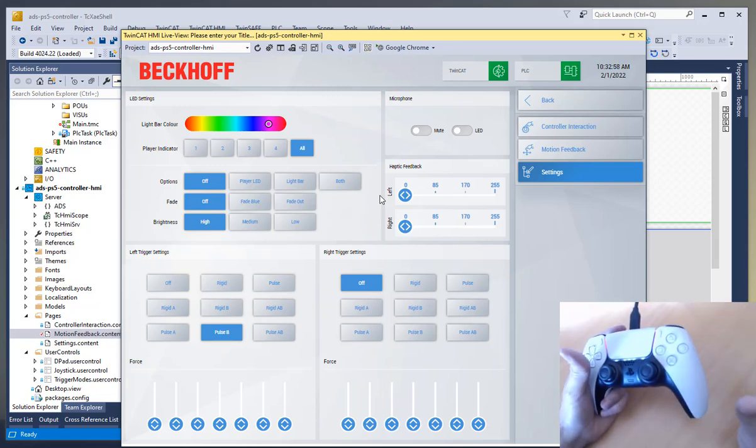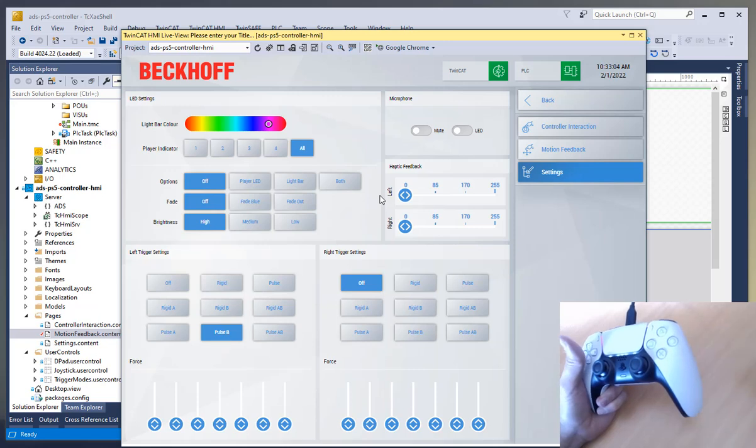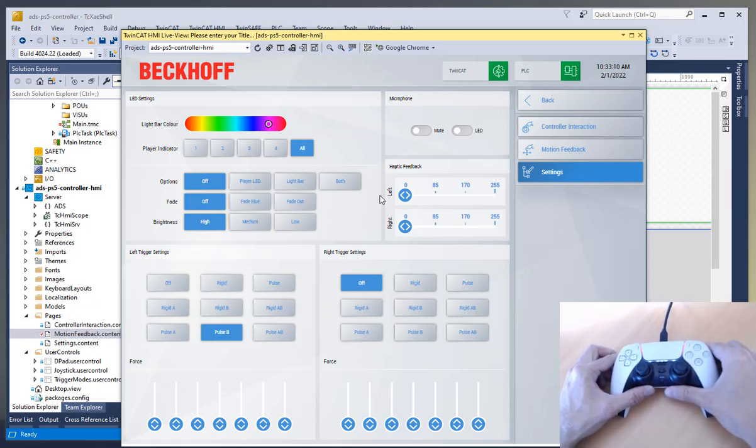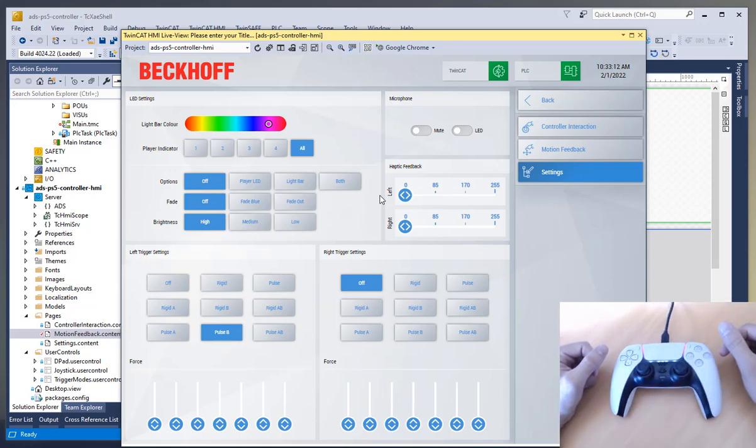As long as it's consistent. I wouldn't just throw things in for rumble's sake. Oh, it rumbles because of this, it rumbles because of that. And you make too many things do the same thing, because just bear in mind, I see that a lot with lamp towers on machines, that the lamp towers themselves end up confusing people. There's too many lights, there's too many things going on. Keep it simple, keep it consistent, and I think you're going to have a really, really good setup with this.